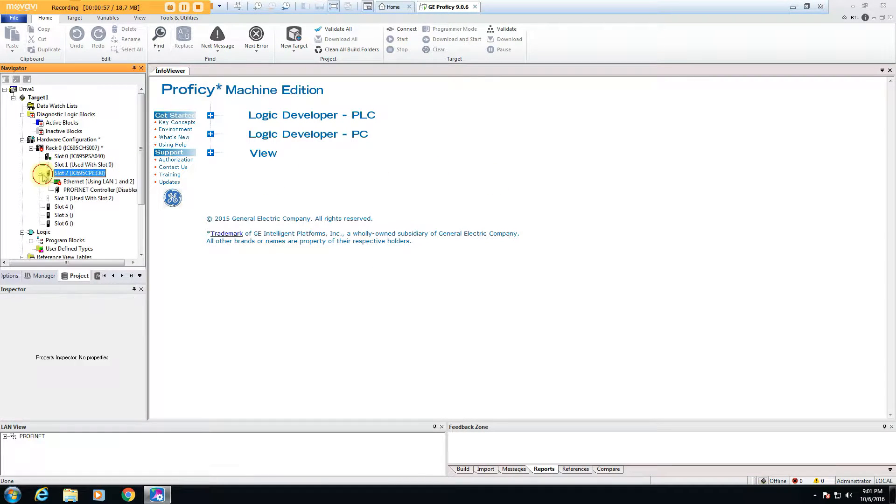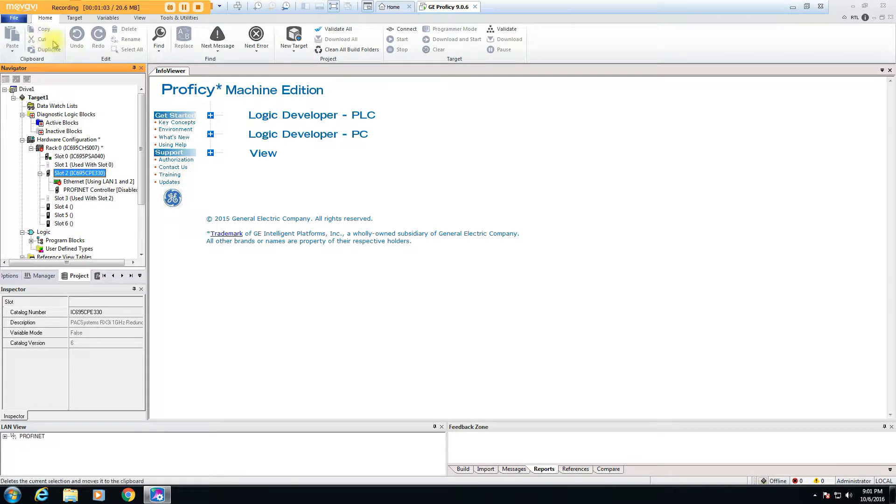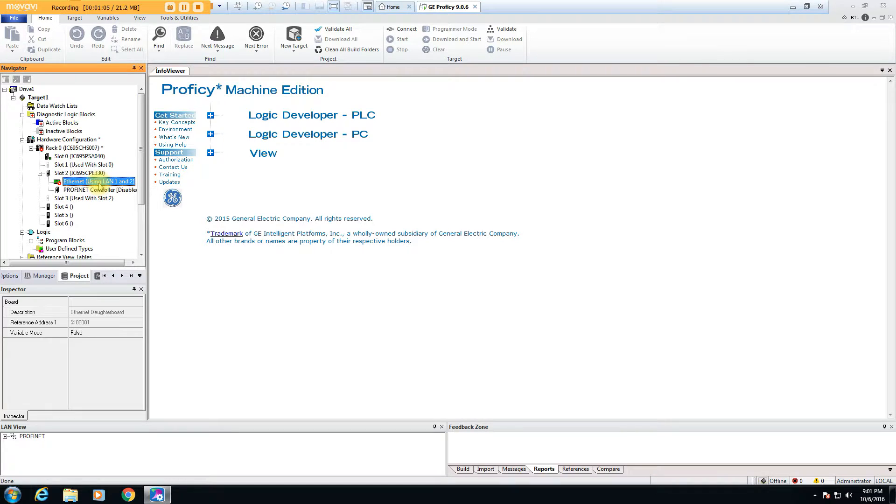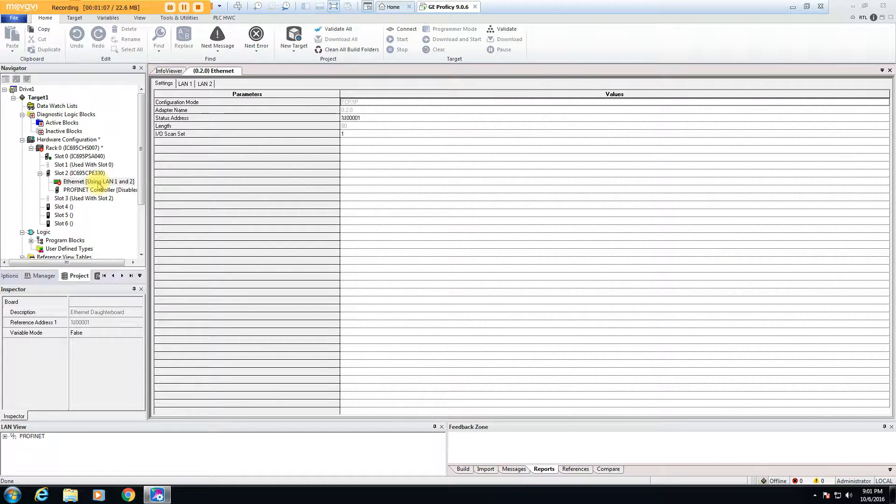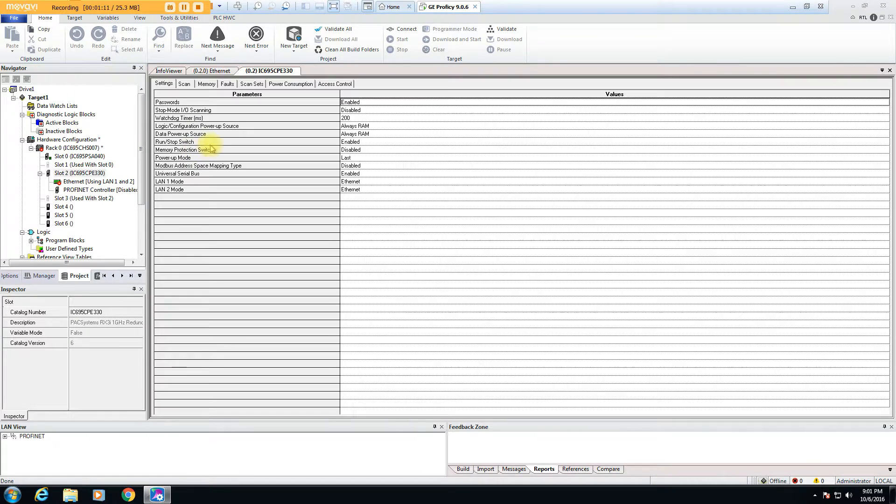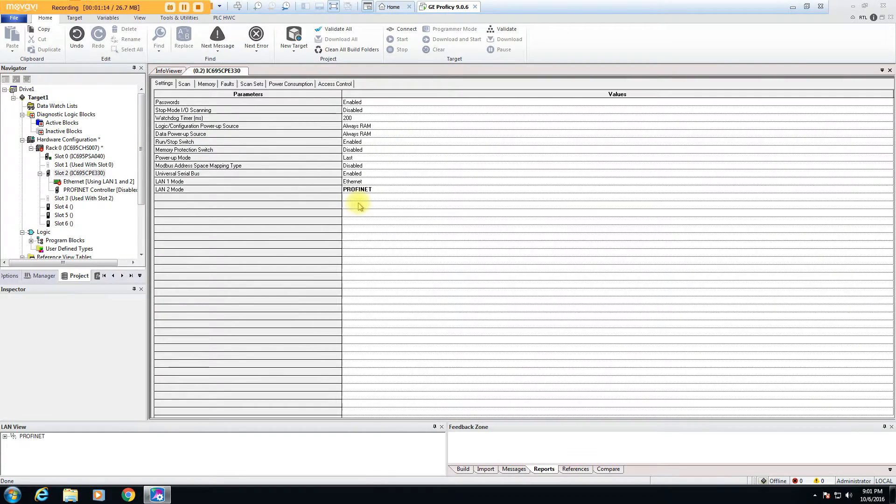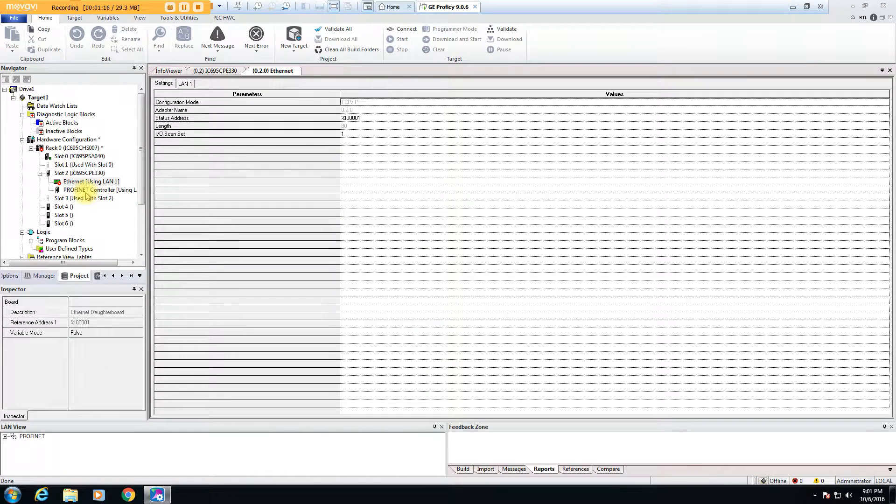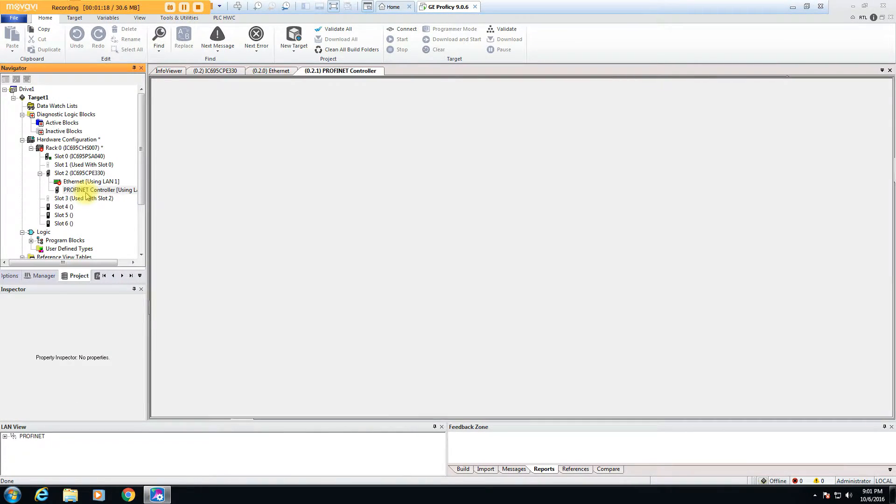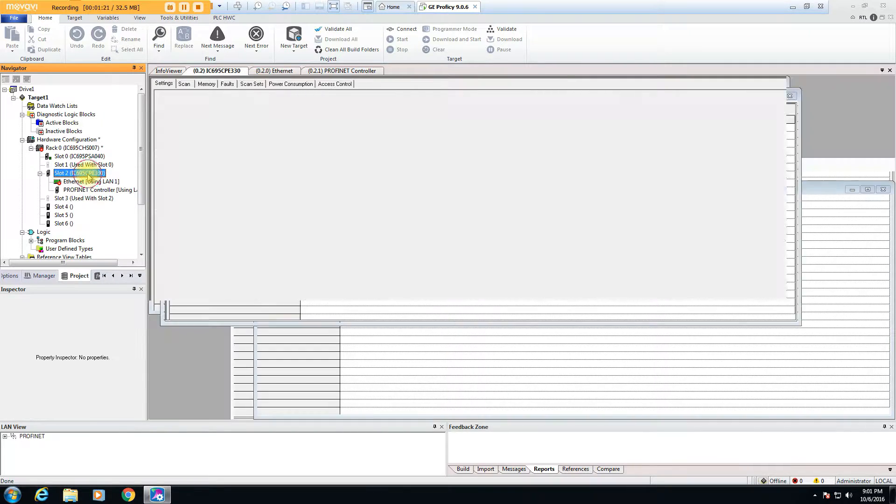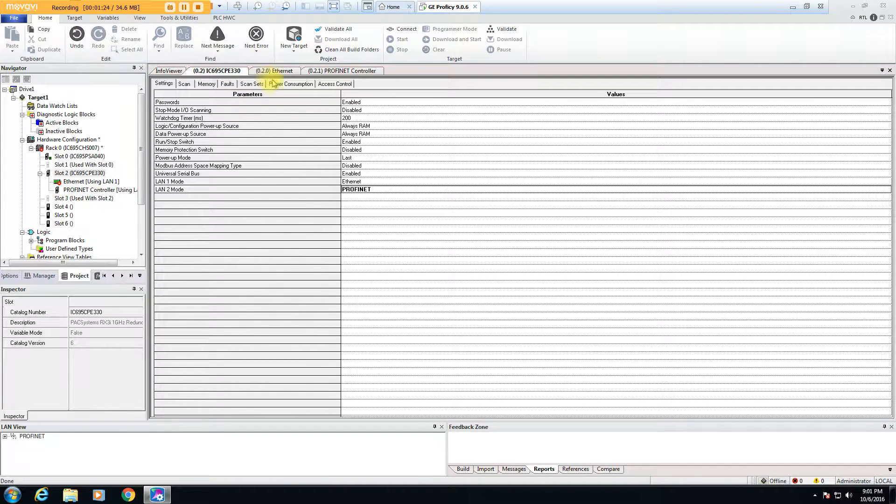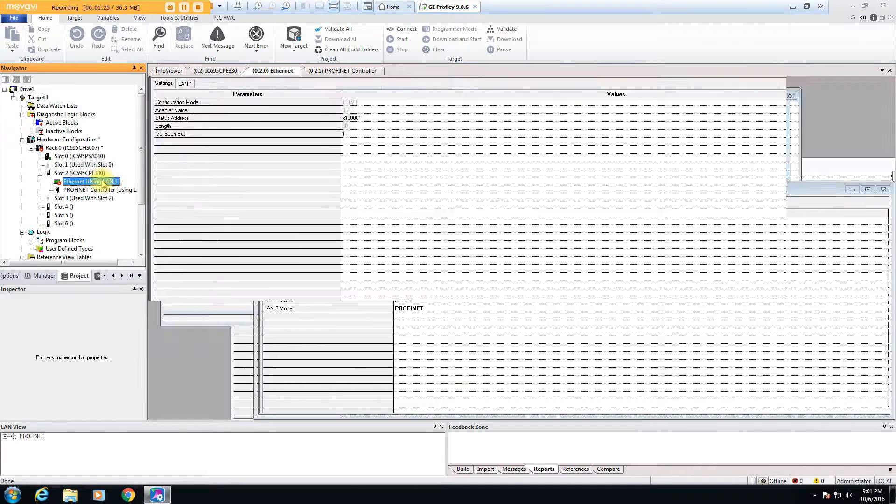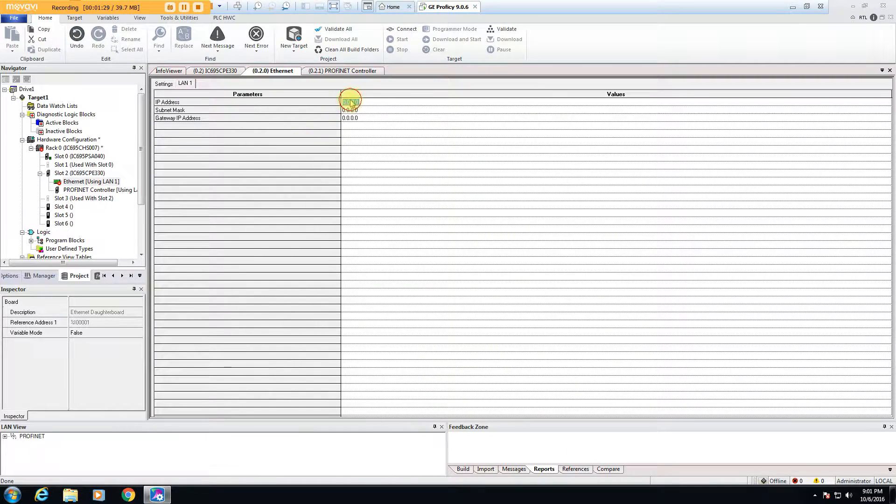Go ahead and configure the project for the correct Rack processor that you're using. In this case, this processor has a regular Ethernet port for programming and other Ethernet connections. It also has a built-in PROFINET port, so you have to set the PROFINET ports to PROFINET, otherwise they're just Ethernet ports. Then you need to set the addresses.